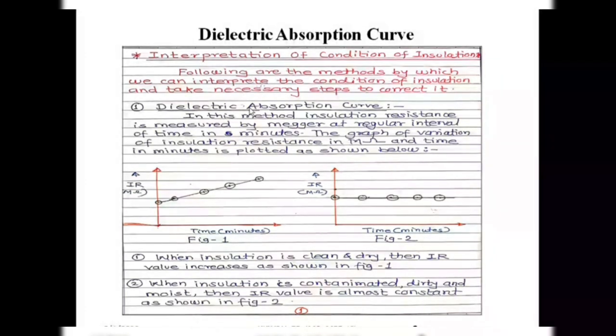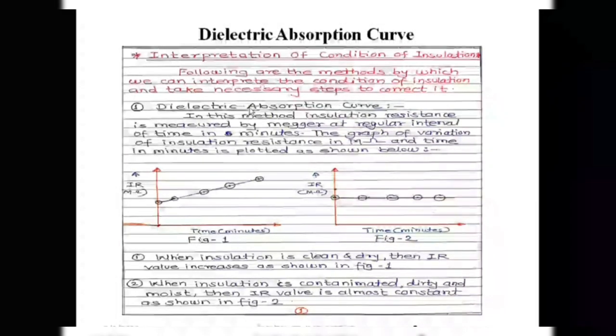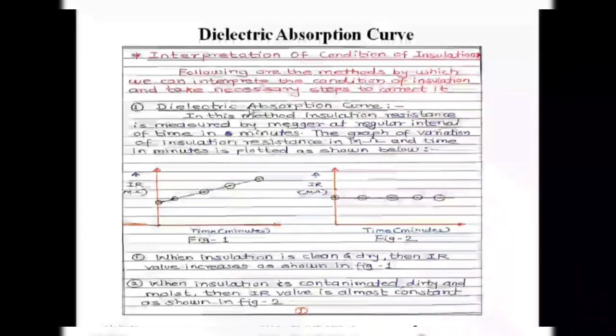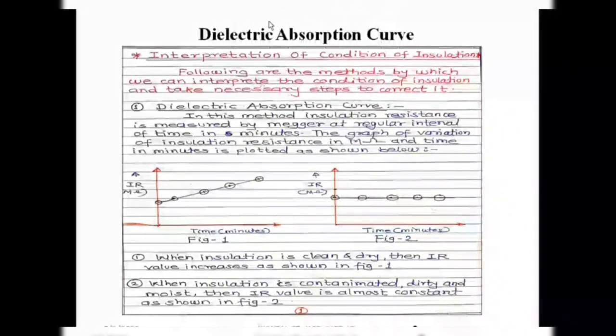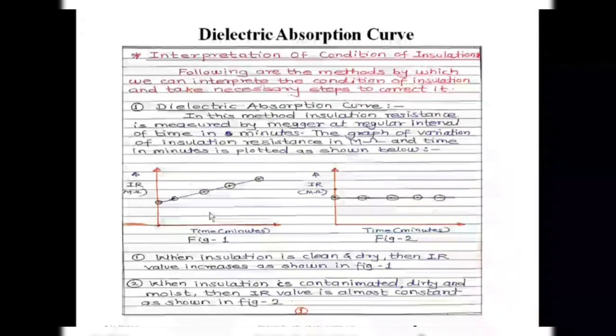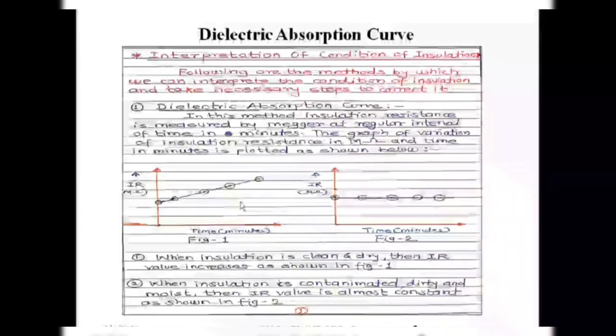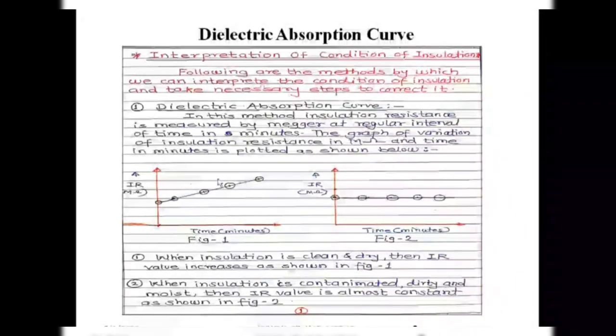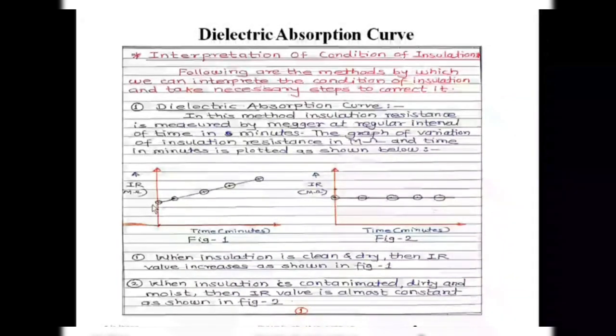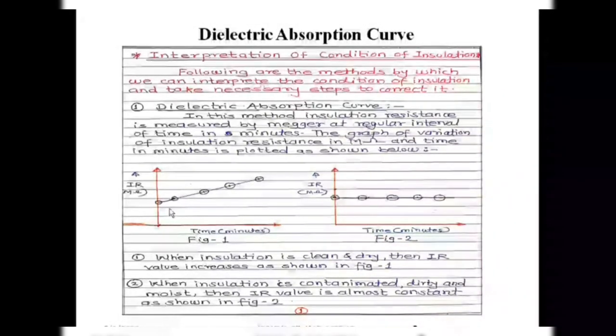First, we'll take the dielectric absorption curve. To plot this curve, we take readings of the insulation resistance of the windings of the given electrical equipment or machine. Readings are taken every one minute after starting the megger test — at least five readings are needed. On the x-axis we plot time in minutes, and on the y-axis we plot insulation resistance in megaohms as measured by the megger.